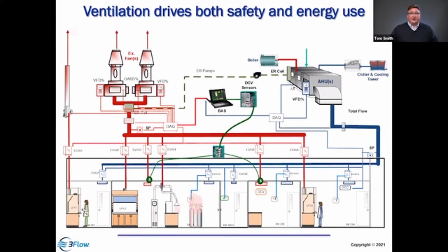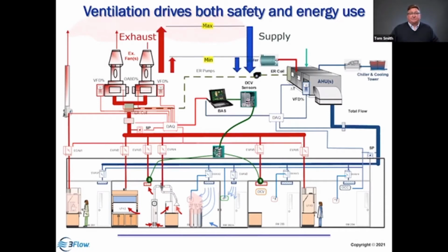So let's bring our occupants in, and now they start working in the hood, and we get our flow through the system, and we anticipate that all of these things are working properly and protecting the occupants. So if we then are modulating flow from minimum to some maximum flow, we expect to see the air handlers and the exhaust fans modulate that flow. They should be in balance. The exhaust flow should equal the supply flow.